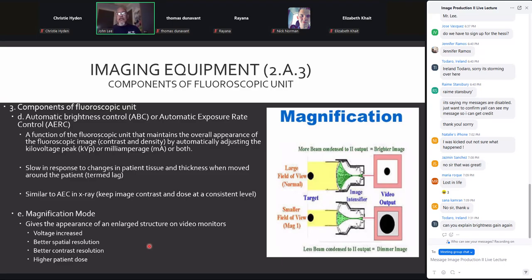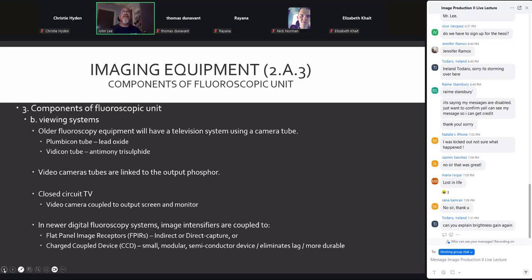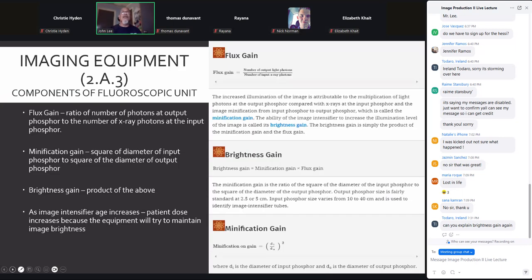Mag mode allows for magnification of the structures during the study. Now, this changes because the minification gain changes. Okay, I'm going to go back to that formula of minification gain so you can see what I'm talking about. Let's use simple numbers here for minification gain, okay? If we start off with no magnification, with an input phosphor size of 20 centimeters, okay? And our output phosphor size is 5, right? 20 divided by 5 is what? 4. 4 squared is 16, right?